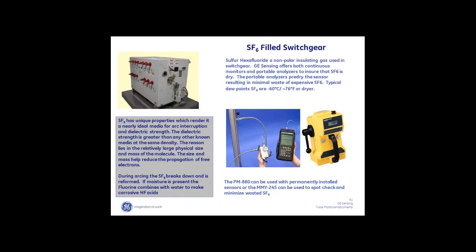In switchgear, SF6 — sulfur hexafluoride — is an insulating gas. The theory is that it quenches arcs: when a big contactor in an electrical enclosure closes, the sulfur hexafluoride quenches the arc and prevents it from propagating. What happens is the molecule blows apart, and if there's any water, it combines with fluorine to form hydrofluoric acid, which is very corrosive. Typically the probe would be installed permanently inside the contactor and a portable is used just to spot-check, since SF6 is a very expensive gas and you don't want to waste it.